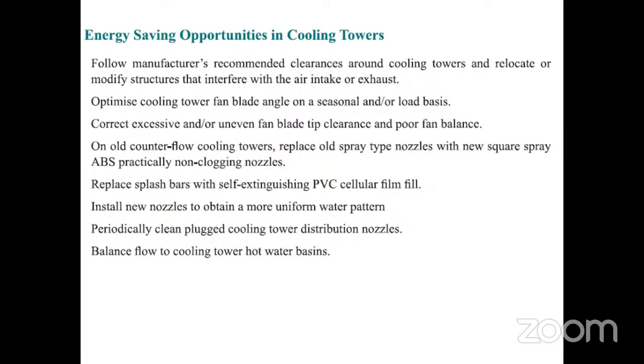First one is the manufacturer's recommendations. Recommended clearances around the cooling towers. There should not be trees or structures or buildings in the surroundings, as they may interfere with the air intake. Optimize the cooling tower fan angle. These are all design parameters. Correct the excessive uneven blade tip clearance and poor fan balance.